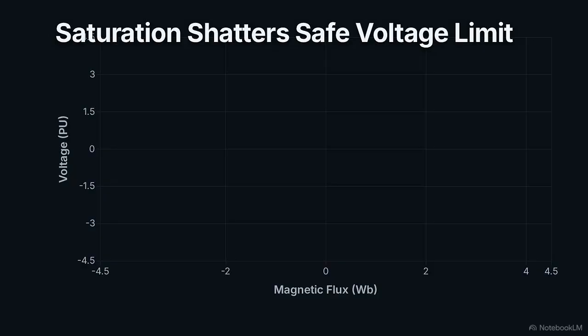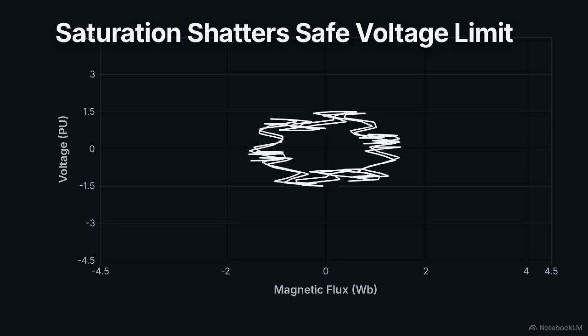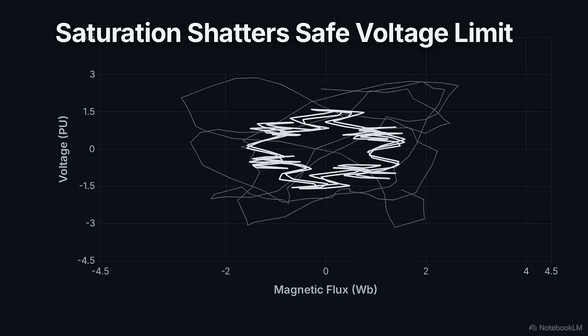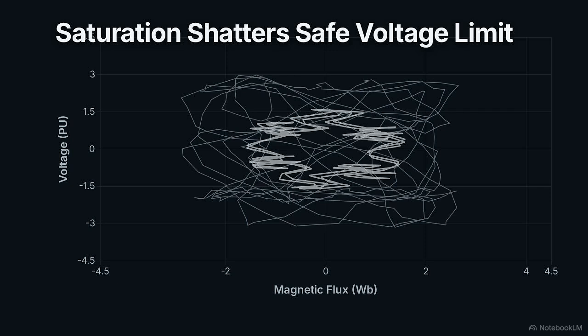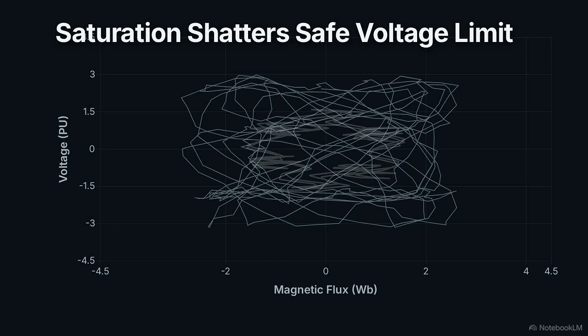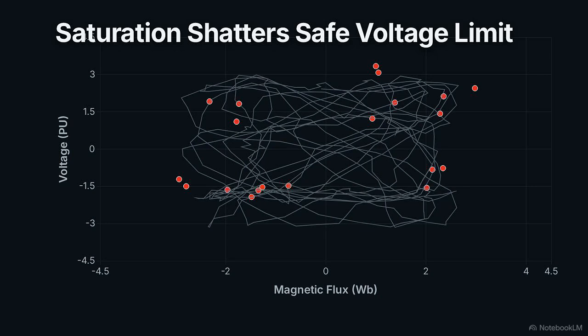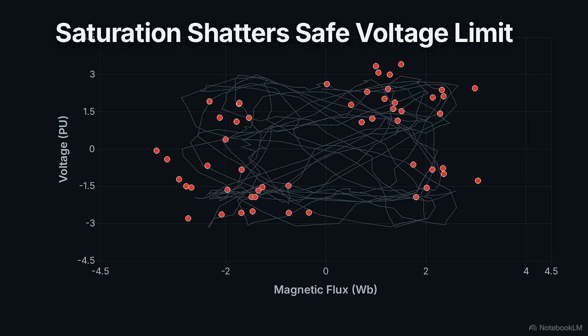This interaction is driven by a transformer with a nonlinear core. As the energy loop intensifies, it pushes that core past its magnetic limit, a state called saturation. At this point, the physics of the system change instantly. The clean, repeating cycles of energy shatter, warping into a rare and erratic phenomenon known as chaotic ferroresonance. In this state, the electrical system is operating entirely unpredictably. It begins bouncing through erratic voltage spikes, unable to bleed off the trapped energy.